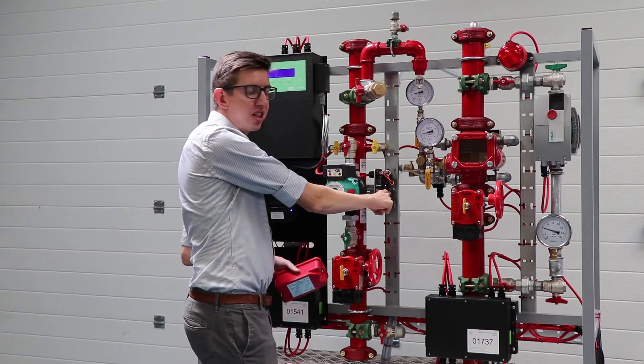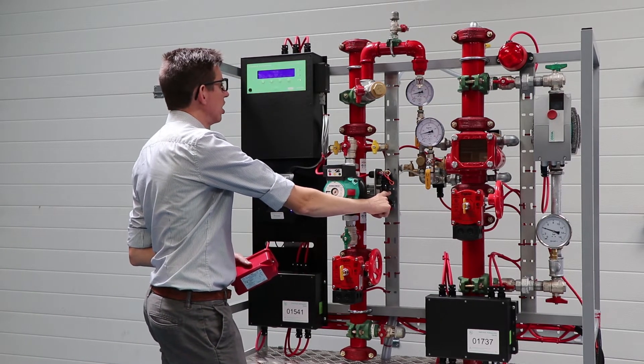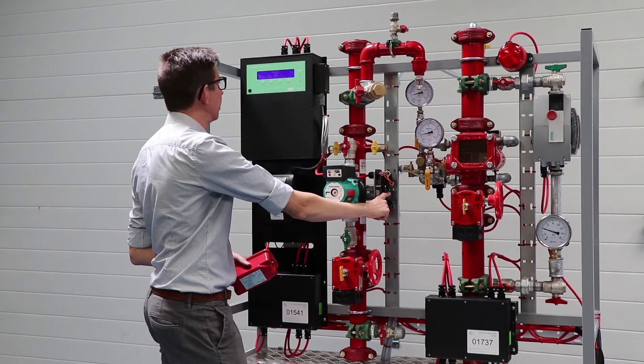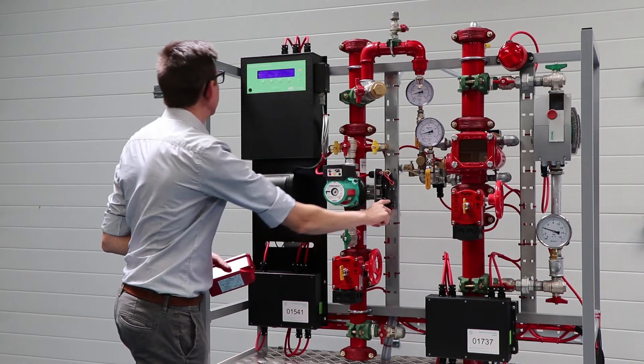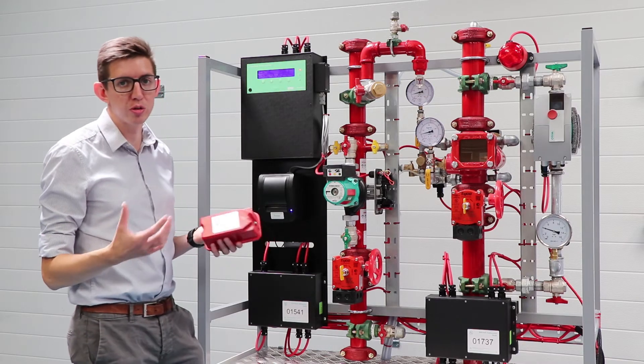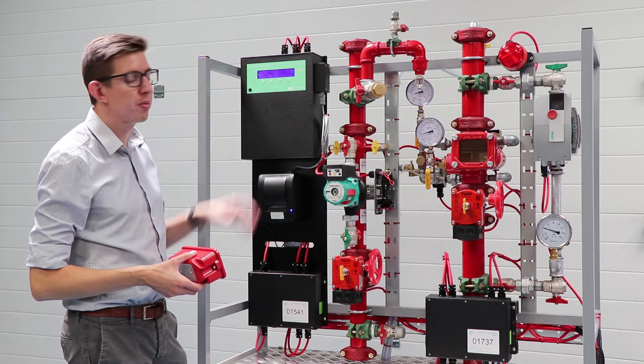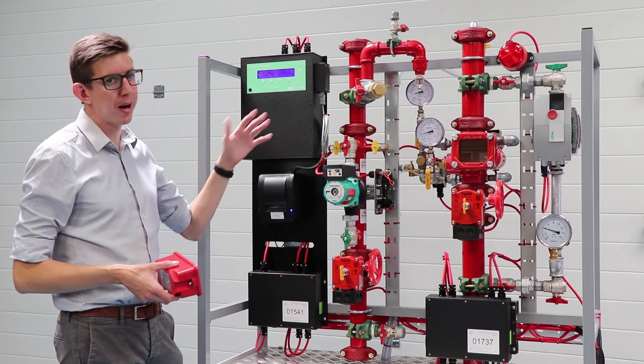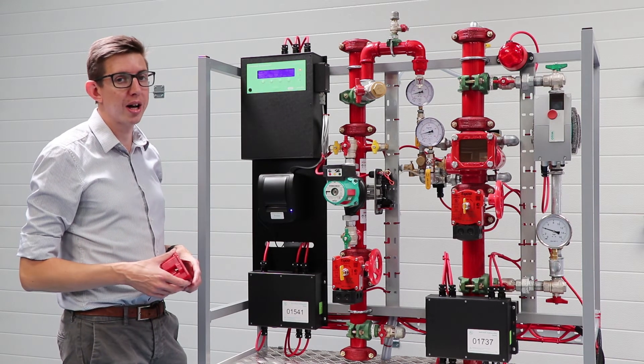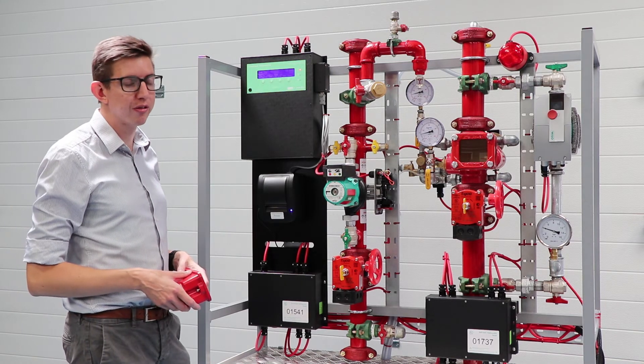I've got to hold this down for 16 seconds because there's a delay on the flow switch. Once it's been held down for a certain amount of time, the flow switch will activate and set the system into fire. You can see here on our controller it's gone into fire mode — this red icon here. It tells us exactly where in the building that is and which is the first flow switch to activate, so any fire responders can see exactly where in the building the fire is. That fire signal can be passed on to BMS systems, conventional fire alarm panels, and our IDENT panel.